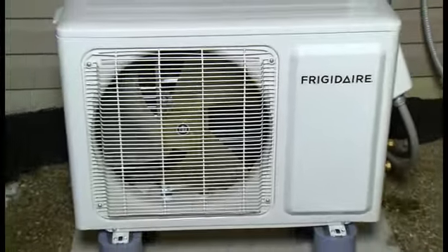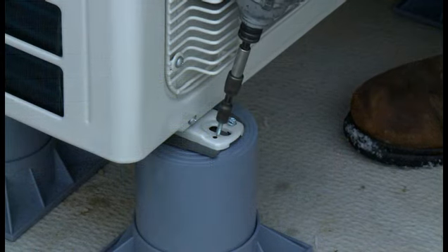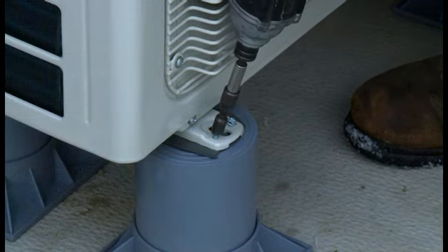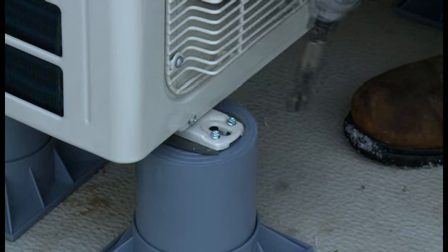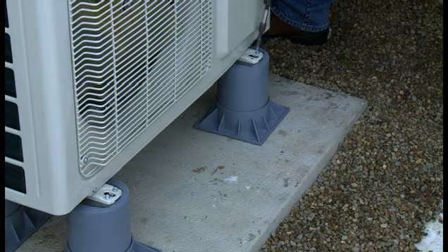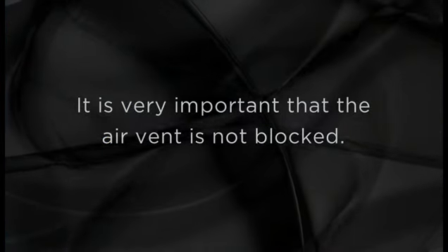To avoid excessive noise or vibration, install the outside unit on a solid or rigid surface at least 12 inches from the structure's foundation. Corrosion-resistant plastic risers, designed for heat pumps and air handling units, are recommended. These are available at most HVAC supply stores. Make sure the air vent is not blocked.